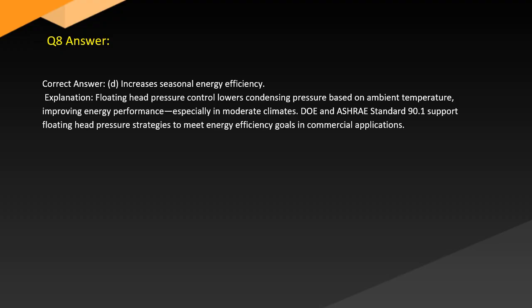Answer. Correct answer: D. Increases seasonal energy efficiency. Explanation: floating head pressure control lowers condensing pressure based on ambient temperature, improving energy performance, especially in moderate climates. DOE and ASHRAE Standard 90.1 support floating head pressure strategies to meet energy efficiency goals in commercial applications.